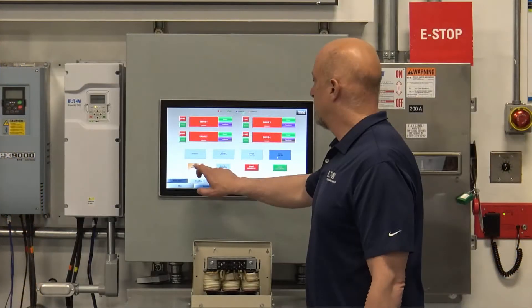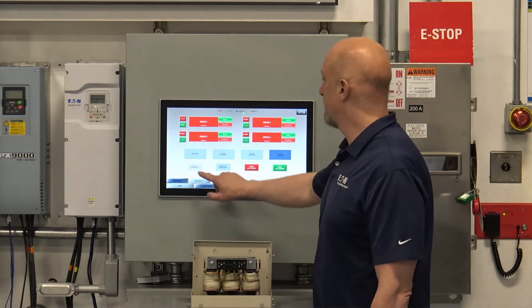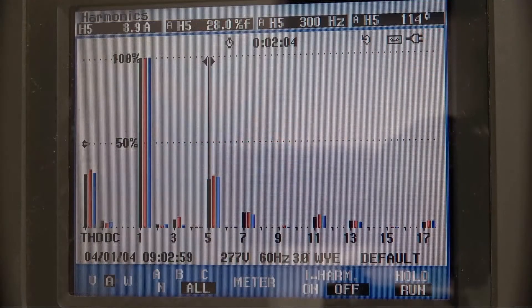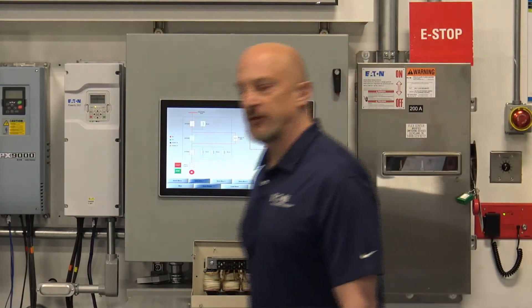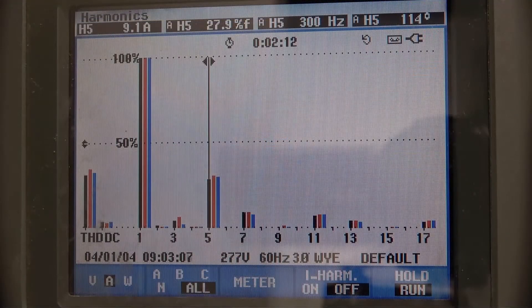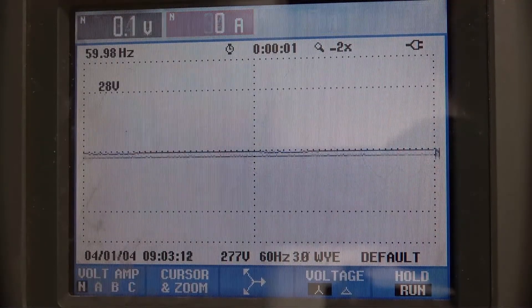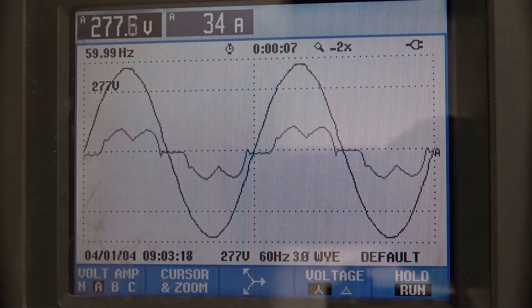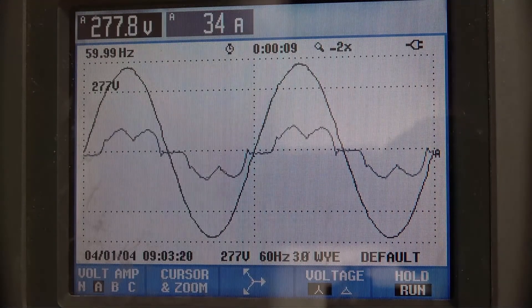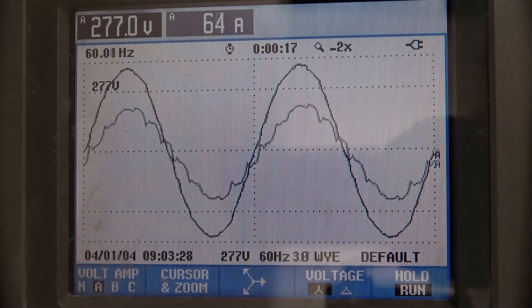With one drive on going through a delta-delta isolation transformer, the harmonics look very similar to what we expect. But when we add the second drive — the one with the 30 degree phase shift through the delta-Y transformer — you can see that now we have what is similar to a 12-pulse situation.